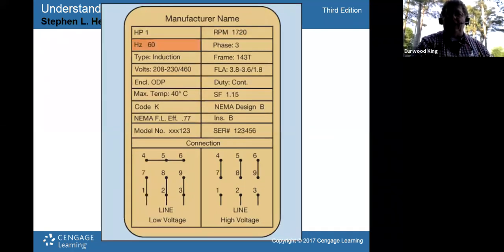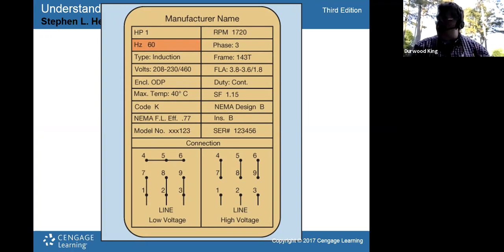The HZ is for hertz. Hertz is the unit for frequency. So that tells you the frequency that it'll accept coming into the motor from the power line or from a VFD. So whatever's running it, if it's straight power line off a motor starter or drive, 60 hertz is the rating on that motor. And if a motor's being used in other countries, in Europe, then it will be 50 hertz, because their power plants run 50 hertz, not 60.